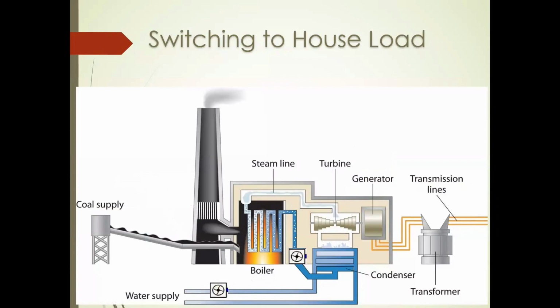Now there is another option if the grid failure occurs from a high frequency situation, only from a high frequency situation. Of course, the generator can switch itself to house load operation when the generator circuit breaker opens. Now, this is not possible in under frequency situations.